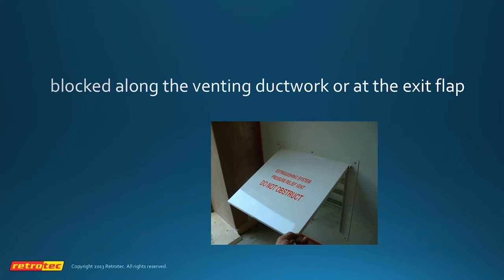Now, the venting path includes the leakage of the enclosure, the leakage of the vent, and the leakage of the duct, if any, to outdoors or wherever it leaks to, or to any rain flap that we're showing here that might be accidentally stuck or whatever. So you can actually measure the complete venting path without even seeing the rest of the venting path. And in this case, we're checking to see that if there's a flap that's being obstructed, it will show you that. So that's a very important test to do upon first installation and on an annual basis to make sure that the venting path is not blocked. If the venting path is blocked in some way, you've lost all your pressure venting.